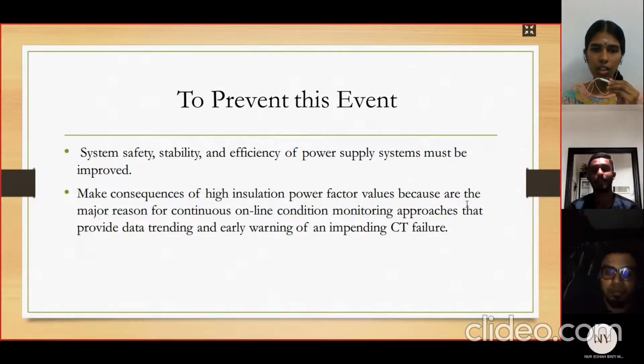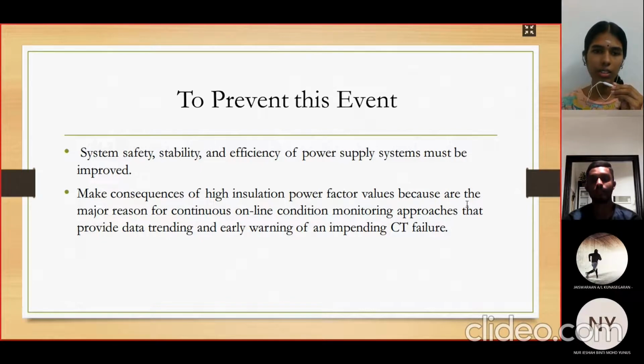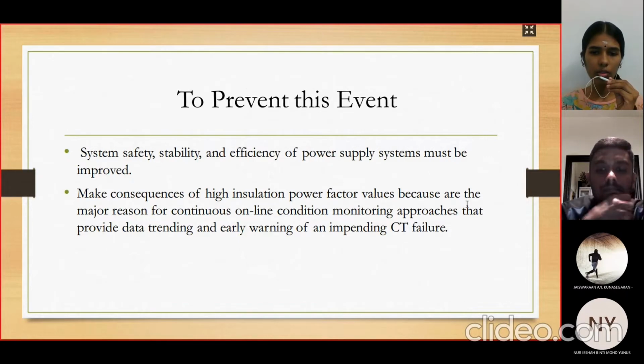Next slide, about how to prevent this event in future. First, system safety, stability, and efficiency of the power supply system must be improved. Second, monitor high insulation power factor values, and use continuous online condition monitoring approaches that provide data trending and early warning of an impending current transformer failure.